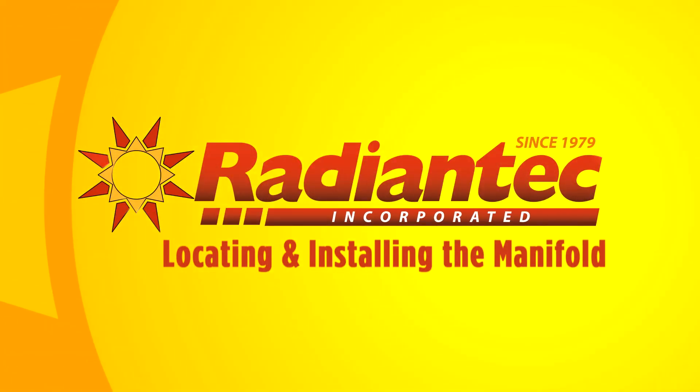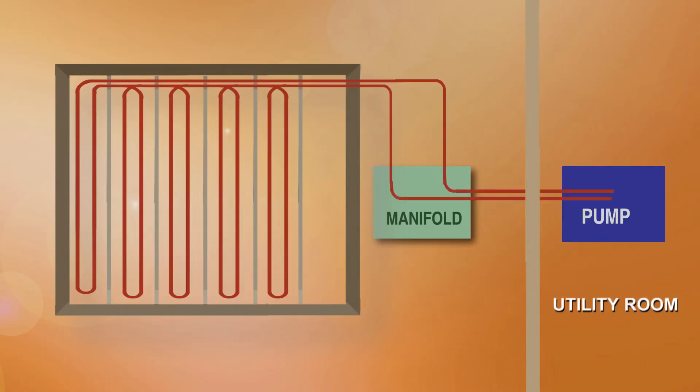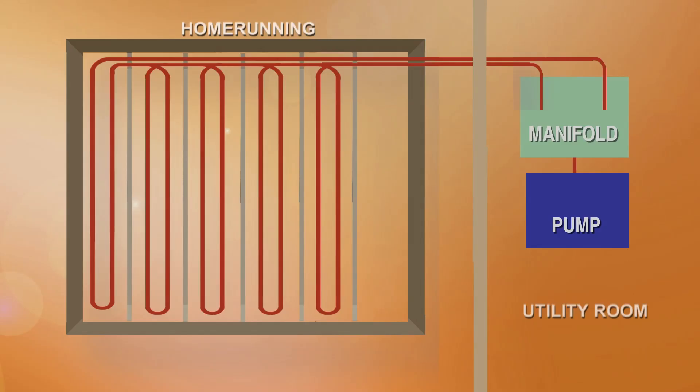The first step in the overall installation is to locate and install the manifold. Radiantec only quotes the amount of tubing required to fill the zone and connect to the tubing manifold located within that zone. We then anticipate that a copper or PEX supply and return line will be run from the pump in the utility room to the tubing manifold and back. Another option is a home run — placing the tubing manifold in the utility room — but depending on the distance, this may require more tubing than originally quoted.